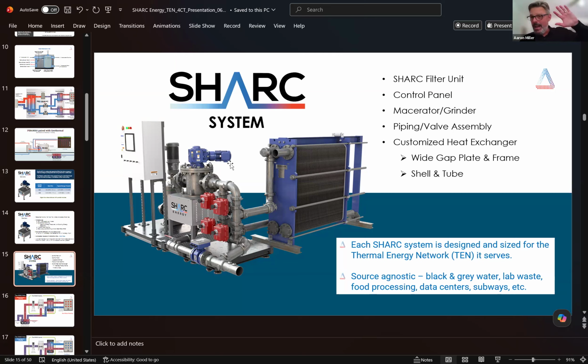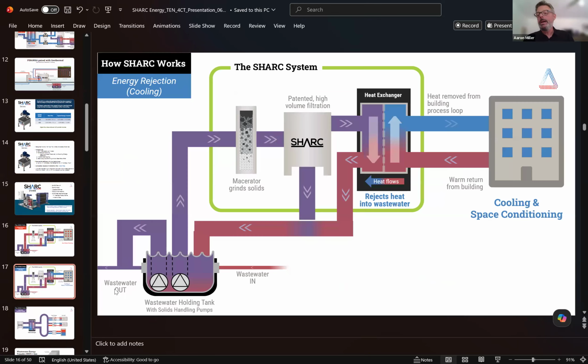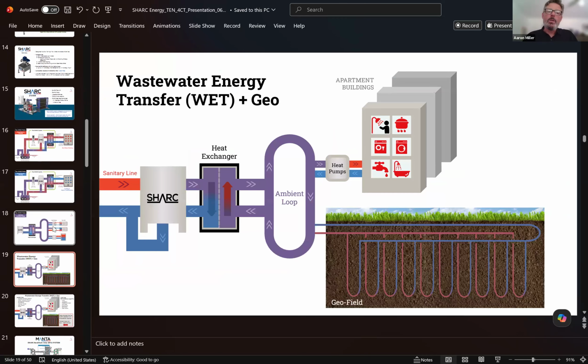And now here, I mentioned before, 100 gallons a minute is my minimum, because the trick is this. I've got a plate and frame heat exchanger with 8 millimeter gaps, and I've got suspended solids about 2.5 millimeters in the water. So by keeping that scrubbing velocity up, keeping that flow up, I can move that sludge through this heat exchanger, do my thermal transfer without any of the stuff dropping out. And knock wood, in 16 plus years, we've never once had to open one of these bad boys up when it's been operated properly.